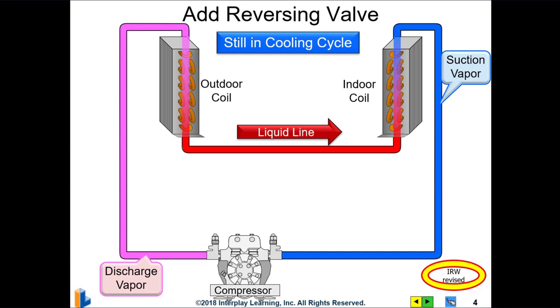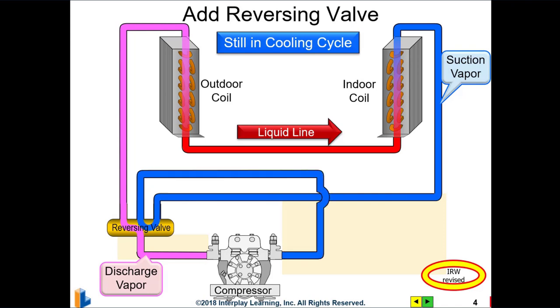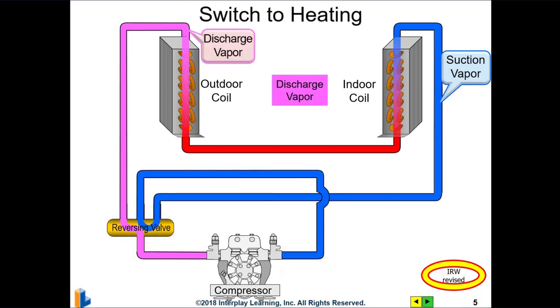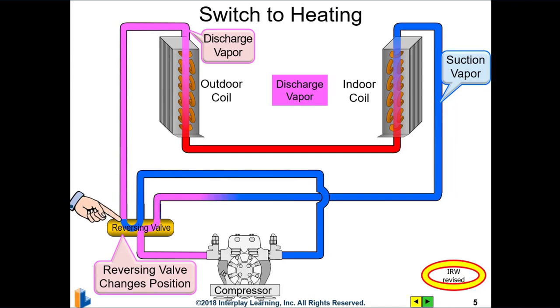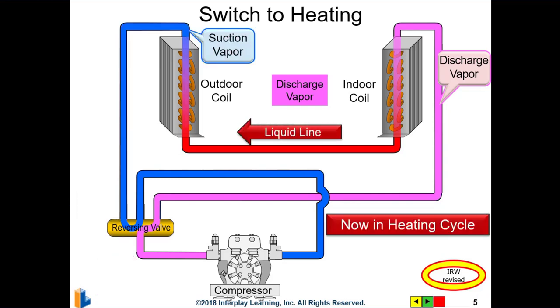If you add a component called a reversing valve, it has the ability to take that discharge gas coming out of the compressor and reroute it — it can send it to the indoor coil. In cooling mode, the discharge gas goes to the outdoor coil, but when we go to heating mode, that valve changes position and the discharge gas gets routed to the indoor coil. The indoor coil is now acting as our condenser, rejecting heat into the space, while heat is absorbed through the outdoor coil from the outdoor air. It's a common liquid line, just flowing in reverse direction in each case.